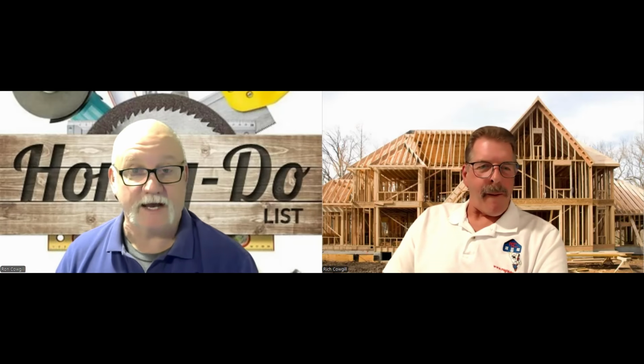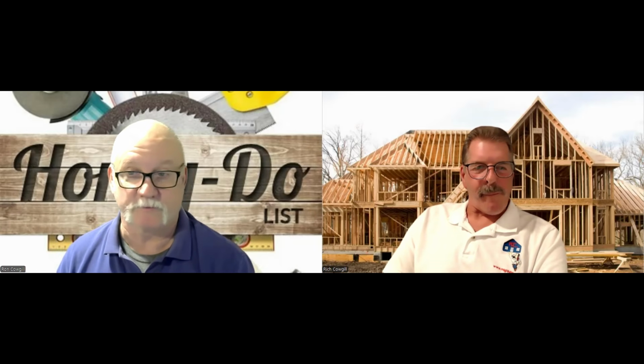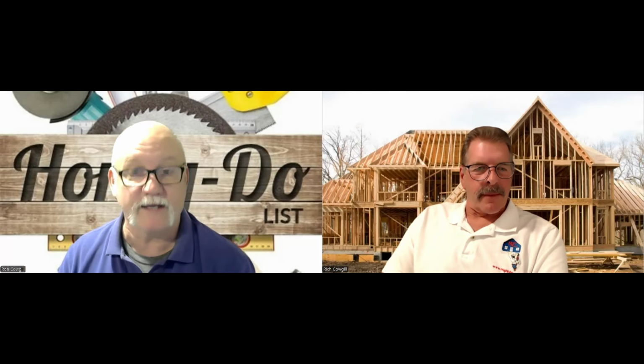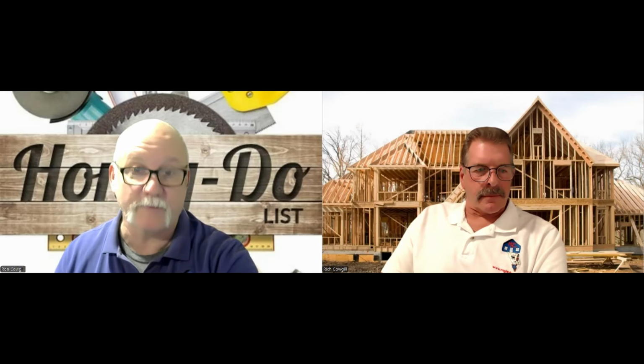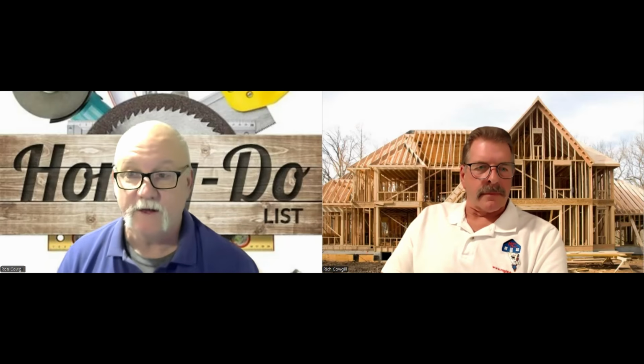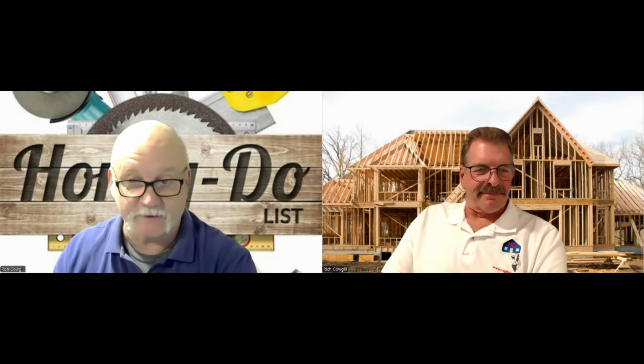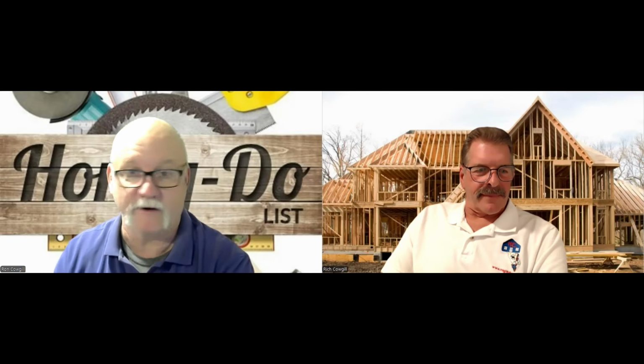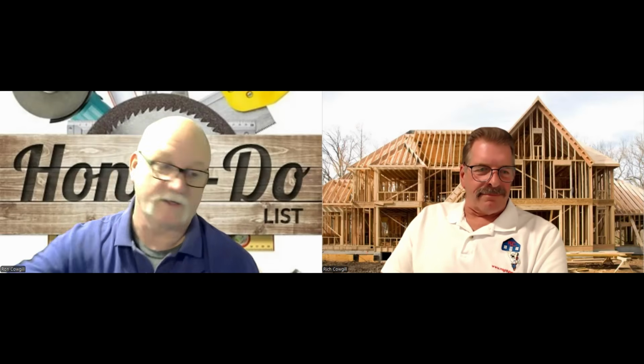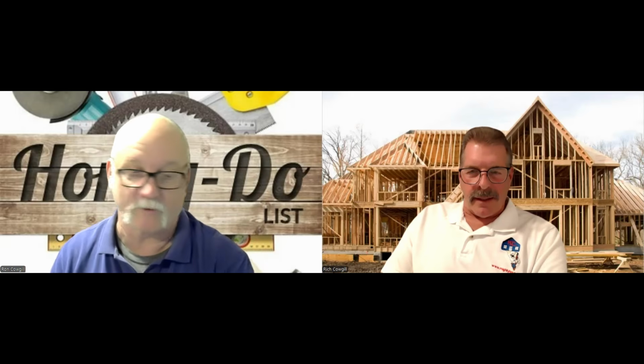We just disassembled a house, a little split level that was built in the late 40s, early 50s. There was some blown-in insulation in the attic, but nothing in the walls at all. The lower attic is open to the upper attic, like what you were showing, and there's also a carport next to it, and that attic is open to the carport too. There was no air barrier into that space. So if the car catches on fire and lights up that roof, it's coming right on through and would go right across the whole attic.